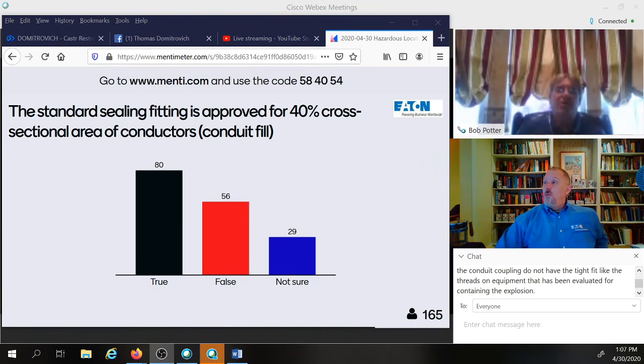The code tells us that your sealing fitting is approved for a 25% cross-sectional fill unless specifically approved for a higher fill rate. So that's where you would have manufacturers producing the expanded fill sealing fitting, which gives you that 40% fill rate.